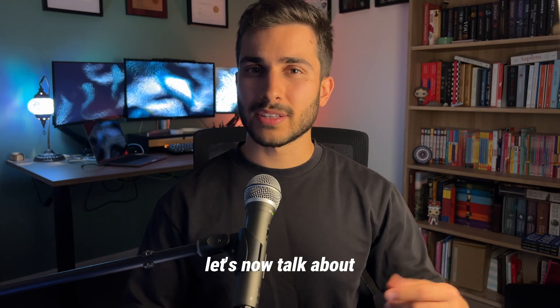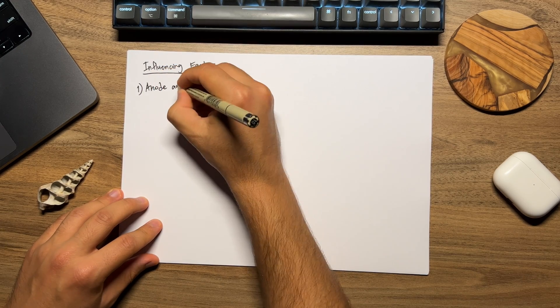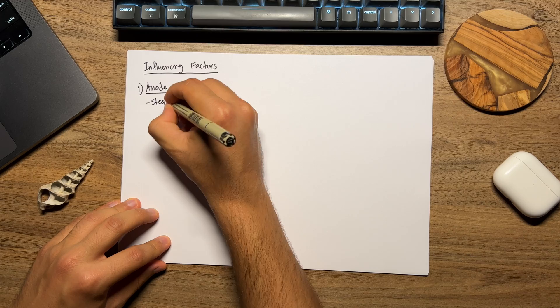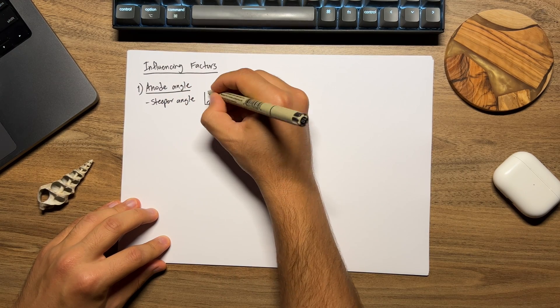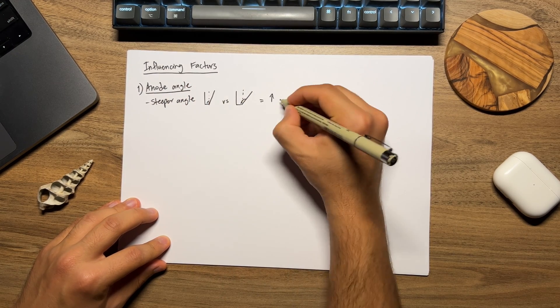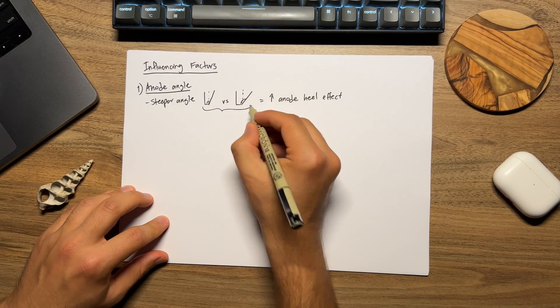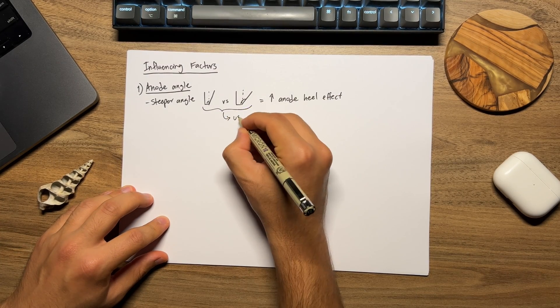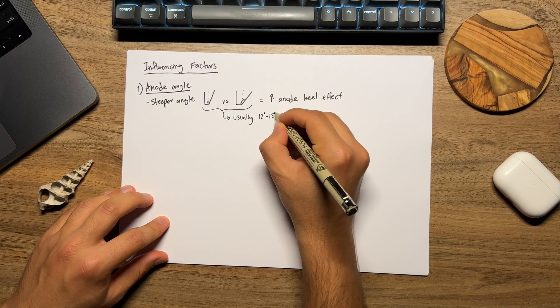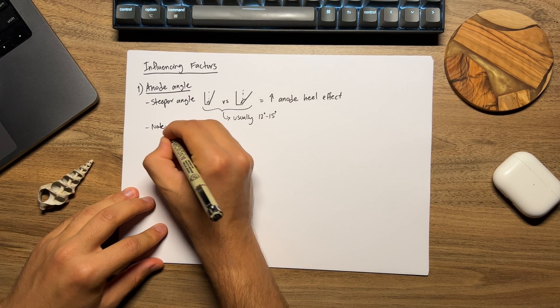Let's talk about the different factors that influence the anode heel effect. The first is the anode angle. The steeper the anode angle, the more pronounced the heel effect. Now this isn't something we can really change — it's set by the manufacturer. They really need to make sure it's an ideal angle, and they usually have it between 12 to 15 degrees, which is probably a lot less than you thought.